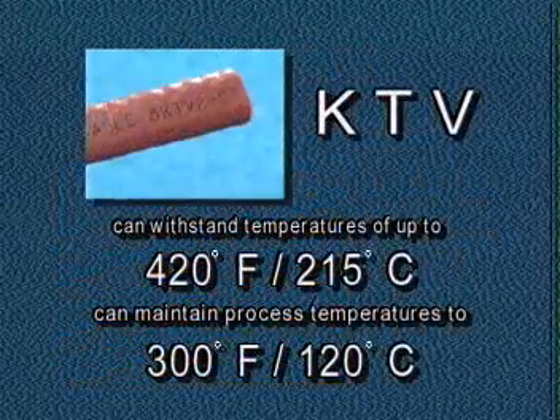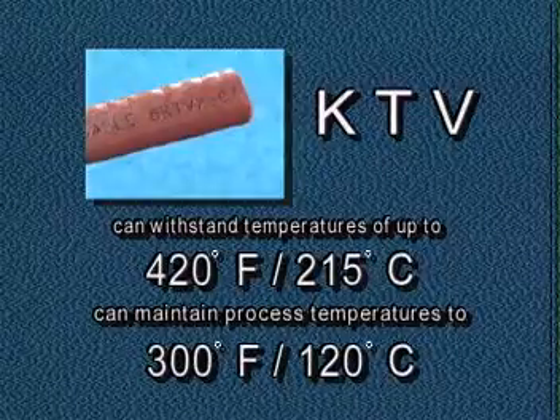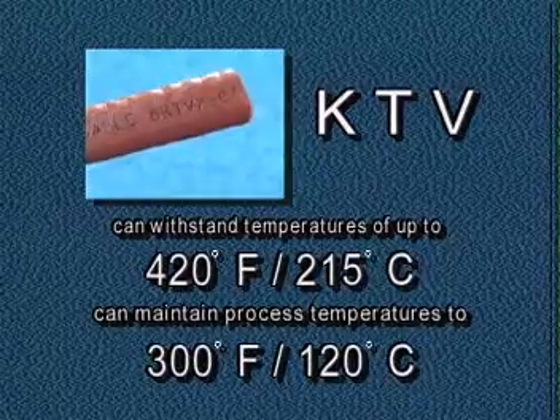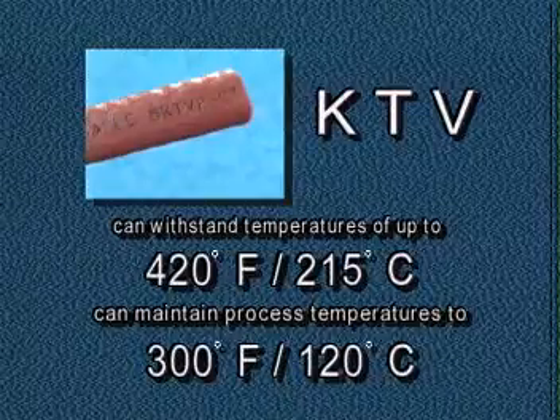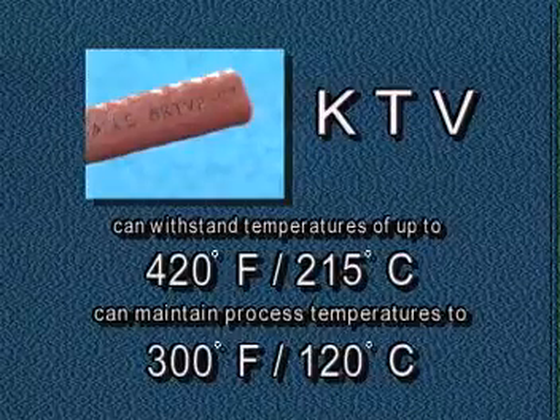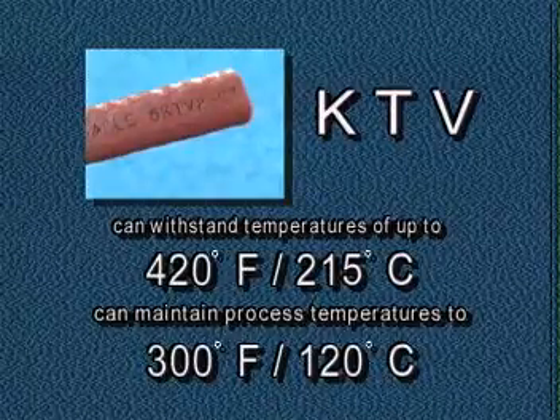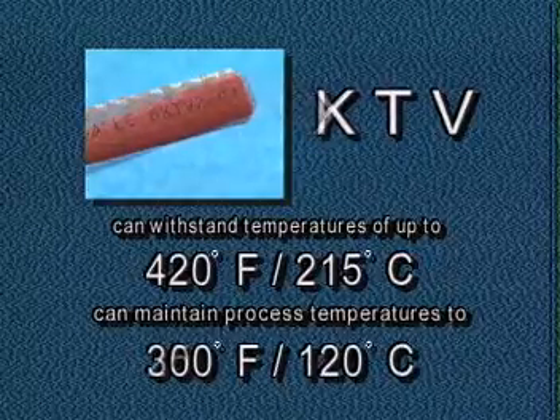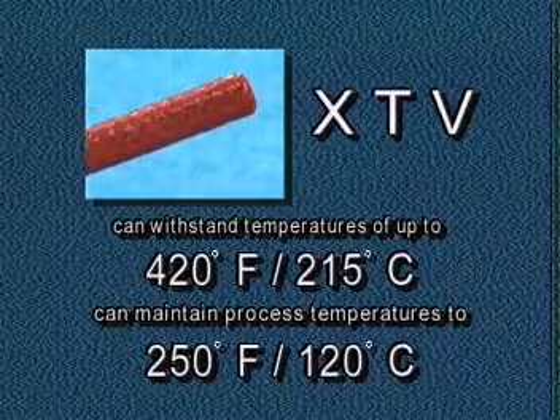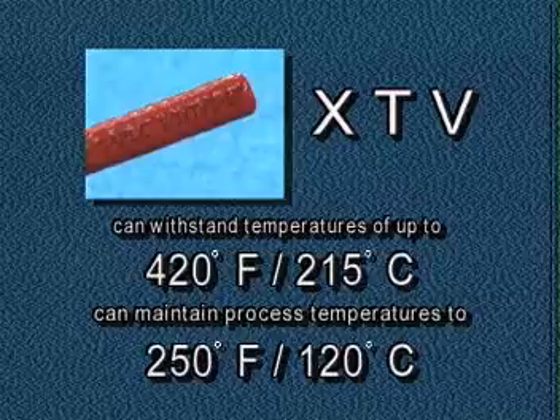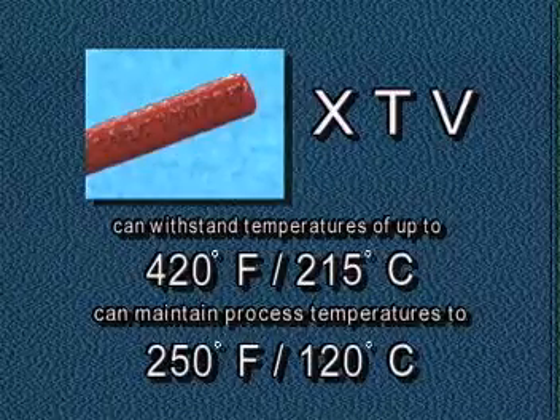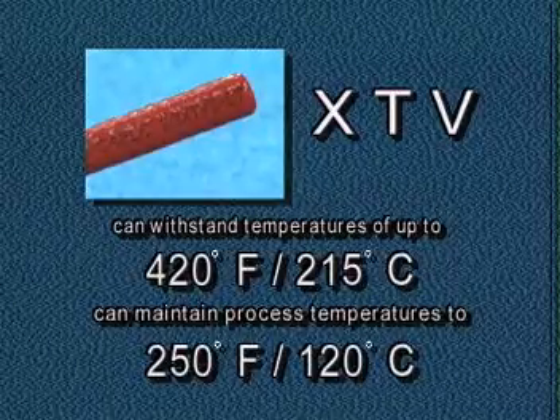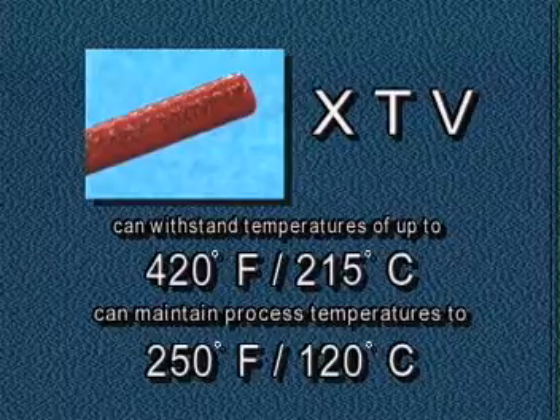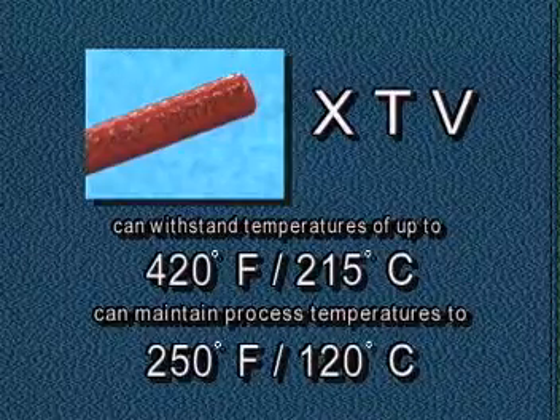KTV cable can withstand temperatures of up to 420 degrees Fahrenheit or 215 degrees Celsius, and it can maintain process temperature to 300 degrees Fahrenheit or 120 degrees Celsius. XTV cable can withstand temperatures of up to 420 degrees Fahrenheit or 215 degrees Celsius, and it can maintain process temperature to 250 degrees Fahrenheit or 120 degrees Celsius.